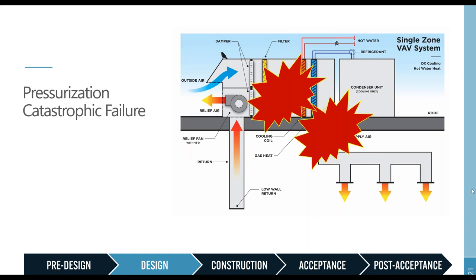And since our commissioning process and our testing process had not yet been completed, this high limit safety switch was not set at the right point and wasn't working correctly yet. And in this case, what actually happened was the supply fan ramped up to 100%, overpressurized the duct, and actually exploded one of the ducts right in the main riser somewhere around the second or third floor in a medical building. So obviously at this time it required a lot of extra work as they now had to replace ductwork inside of the main riser shaft, which was obviously unplanned, as they were getting towards the end and trying to hit occupancy goals.